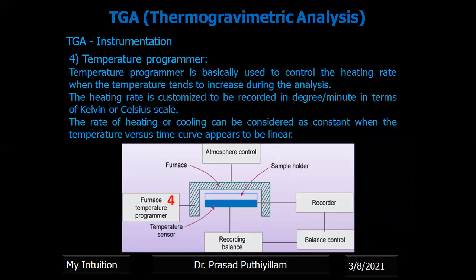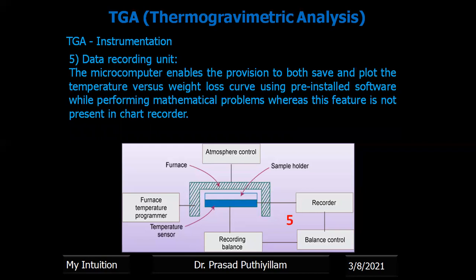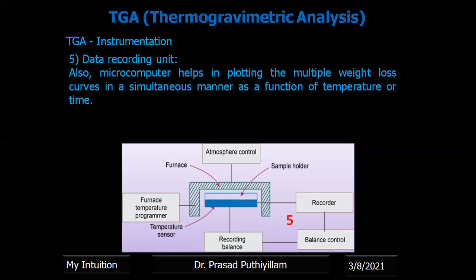The fourth component is the temperature programmer, which controls the heating rate even as temperature increases during analysis. The heating rate is customized and recorded in degrees per minute in Kelvin or Celsius. The rate of heating or cooling is considered constant when the temperature versus time curve appears linear. The fifth component is the recording system or data recording unit, which may be a chart recorder or microcomputer. Nowadays, a microcomputer is preferred because it enables saving and plotting the temperature versus weight loss curve using pre-installed software, and can plot multiple weight loss curves simultaneously.